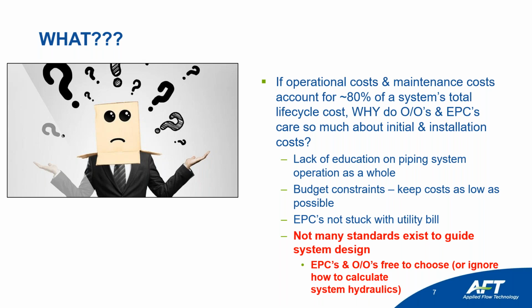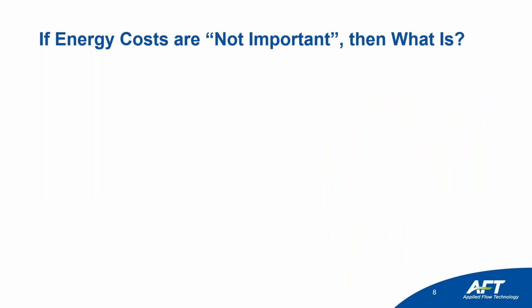And for those that do choose to do the flow analysis, they can choose how they calculate it. So rather than doing a good detailed analysis, they may just be doing back of the envelope hand calculations or rule of thumb methods or Excel spreadsheets. And so there's not any standards in place that really guide a good analysis. And if this was in place, where it would force owner operators and EPC companies to take a better look at their designs, then the systems would run and operate a lot more efficiently and avoid a lot more problems.